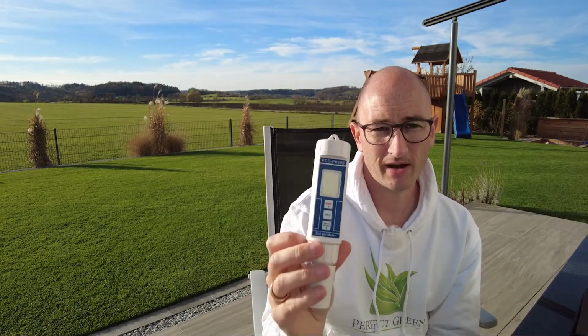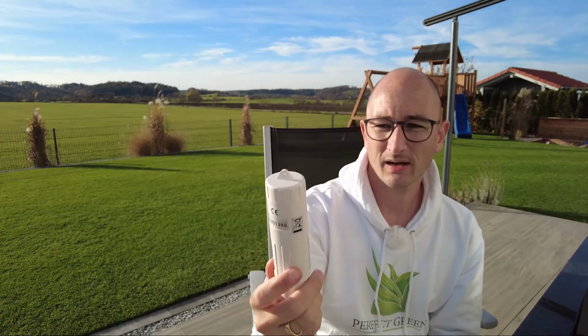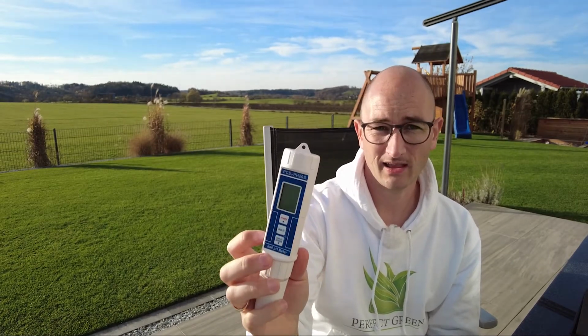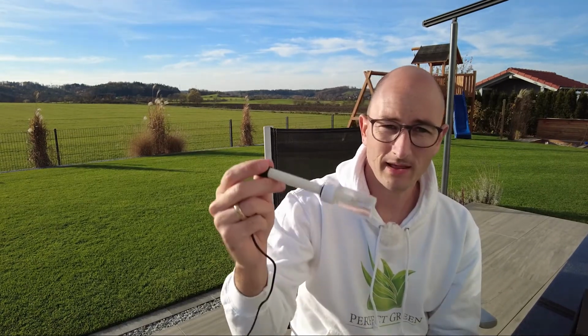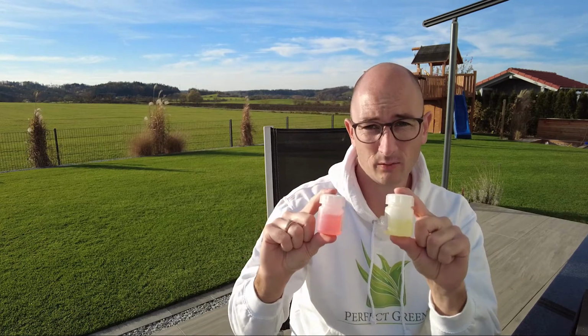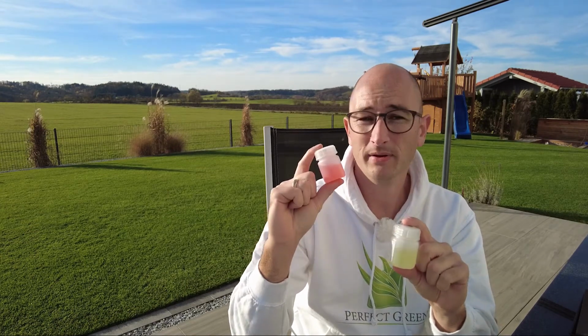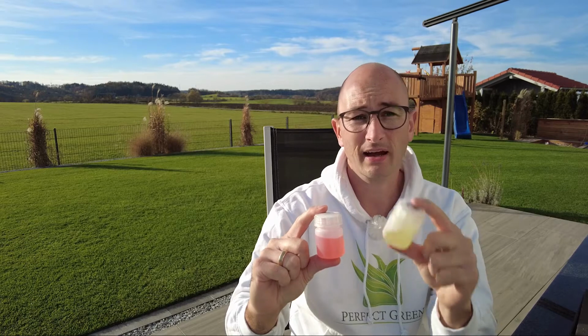When you order this device, what waits for you and what do you get? For one, you get the computer, the PCE PH20S. There's also the measuring probe. And you get, and that is the brilliance of this device, two calibration solutions delivered with it. One pH value 4 and one pH value 7. That has a large advantage.